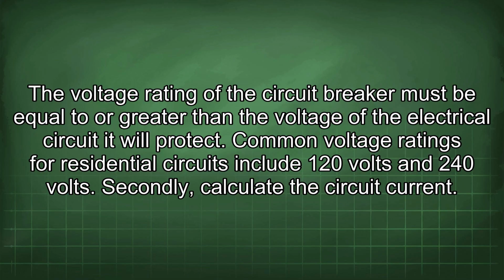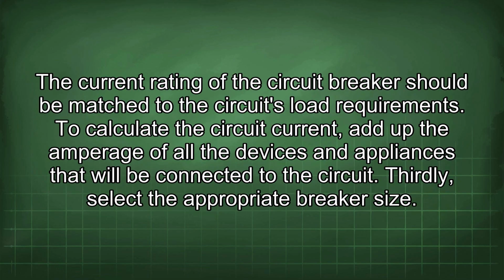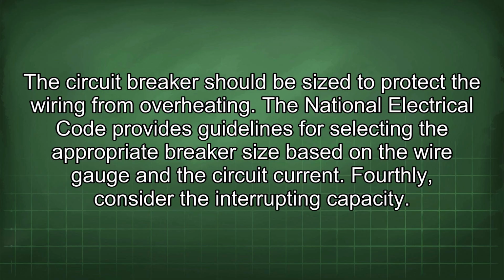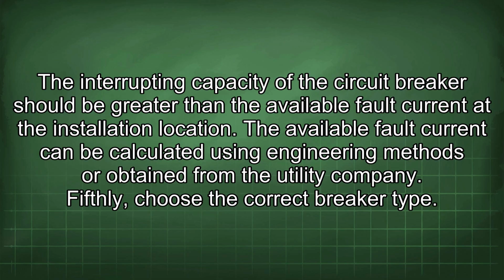Secondly, calculate the circuit current. The current rating of the circuit breaker should be matched to the circuit's load requirements. To calculate the circuit current, add up the amperage of all the devices and appliances that will be connected to the circuit. Thirdly, select the appropriate breaker size. The circuit breaker should be sized to protect the wiring from overheating. The National Electrical Code provides guidelines for selecting the appropriate breaker size based on the wire gauge and the circuit current. Fourthly, consider the interrupting capacity. The interrupting capacity of the circuit breaker should be greater than the available fault current at the installation location. The available fault current can be calculated using engineering methods or obtained from the utility company.